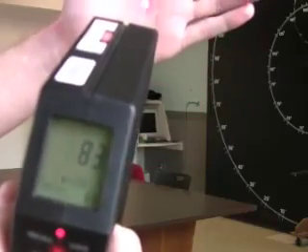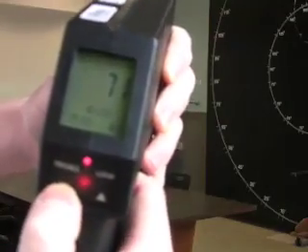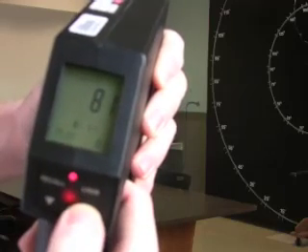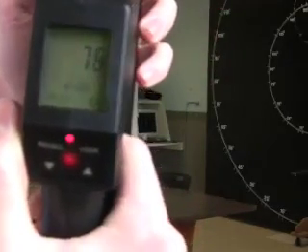What you want to do when you use it is point it at the object you want to measure, and you can flip on a laser sight with this button in the back. That will allow you to see exactly what part of the object you're measuring. Pull the trigger, which will give you the temperature of the object. You can change the emissivity settings on the gun by pressing these arrows, and that will allow you to get a more accurate measurement of the surface temperature than the smaller Raytek gun, which has a fixed emissivity setting.